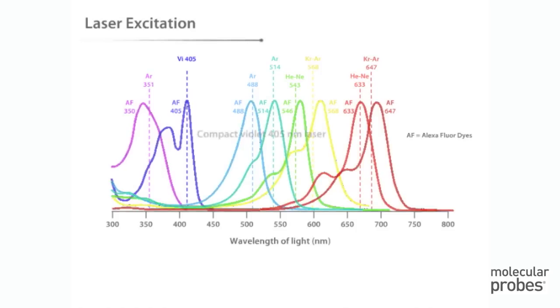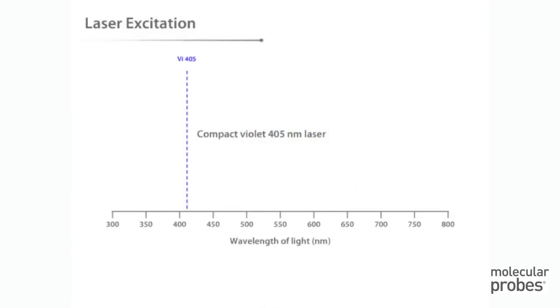Compact violet 405-nanometer lasers are replacing expensive UV lasers for most biological work. The most commonly used lasers are the 488-nanometer blue-green argon laser, 543-nanometer helium-neon green laser, and 633-nanometer helium-neon red laser. Mixed gas lasers, such as the krypton argon laser, can output multiple laser lines, and therefore may still require optical filters to achieve selective excitation.